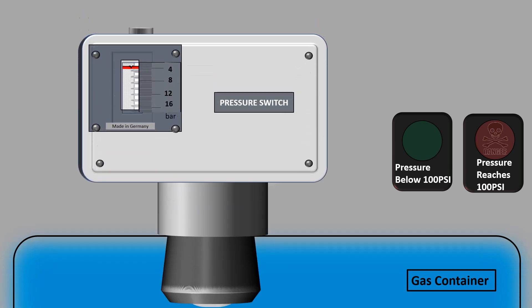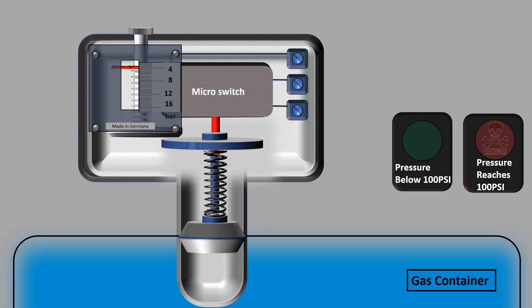Working of a mechanical pressure switch. Consider that we have a gas container and we need a green light to switch on when the pressure inside the container is below 100 psi, and a red light to switch on when the pressure reaches 100 psi. For this we install a pressure switch on this container and adjust the set point of this pressure switch at 100 psi by turning the set point adjustment screw.